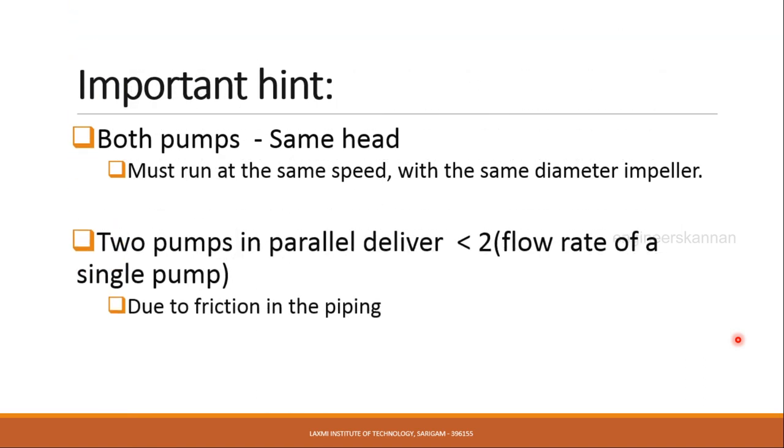Important hints before connecting two pumps in parallel: both pumps should have the same head, run at the same speed, and use same diameter impeller. The major drawback is that two pumps in parallel deliver water which is lesser than two times the flow rate of a single pump, due to increment in friction of particular piping.